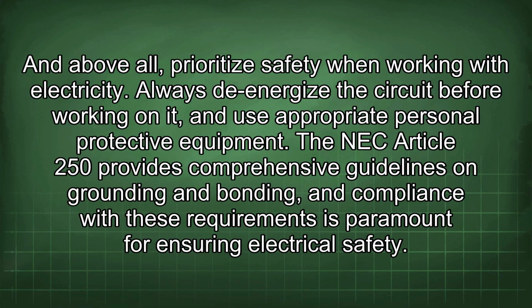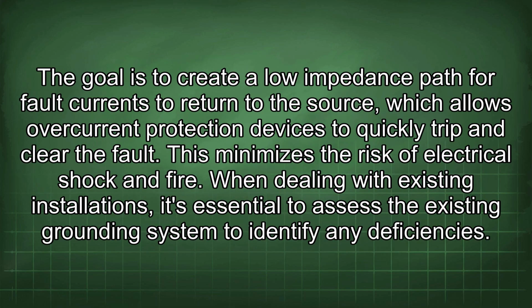The NEC Article 250 provides comprehensive guidelines on grounding and bonding, and compliance with these requirements is paramount for ensuring electrical safety. The goal is to create a low impedance path for fault currents to return to the source, which allows overcurrent protection devices to quickly trip and clear the fault. This minimizes the risk of electrical shock and fire.